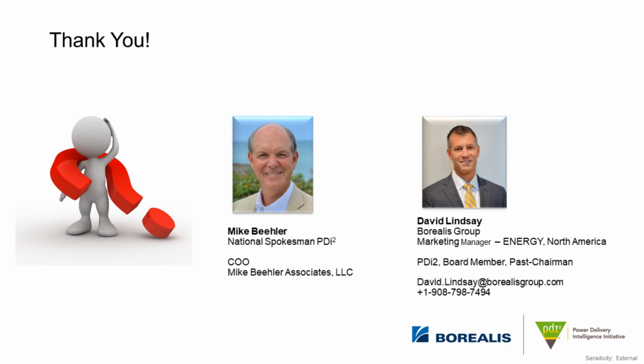Great question. It has changed over the years. When offshore wind began, you had a lot of dry design cables with metallic moisture barriers, in particular lead sheath on them. As offshore wind in Europe has become more and more prevalent, and they've tried to drive the cost out of those systems, they have transitioned to wet design cables. So the cables being used today predominantly are wet design, and that is true even with the voltage levels going up from 33 kV to 66 kV, as I mentioned, with the turbines getting bigger.